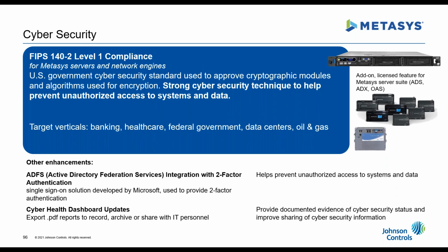A very important feature at Metasys 11 is FIPS 140-2, the Federal Information Processing Standards. This is a standard we see in U.S. federal government specifications, and we're starting to see it more in other vertical markets too, like banking, data centers, and hospitals. It's a type of encryption and security technique that your product is certified as employing to offer further security within the building automation system. Any of our products at the supervisory level that come with Metasys 11 out of the factory will have this automatically, as will any existing engines or supervisory controllers upgraded to 11. That's level 1 compliance certification at that level.